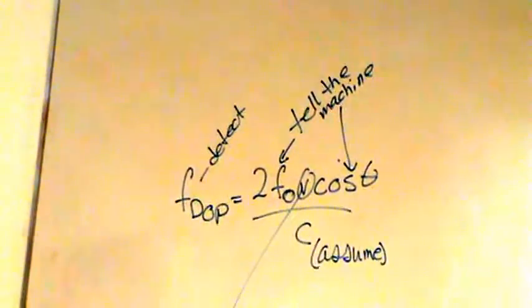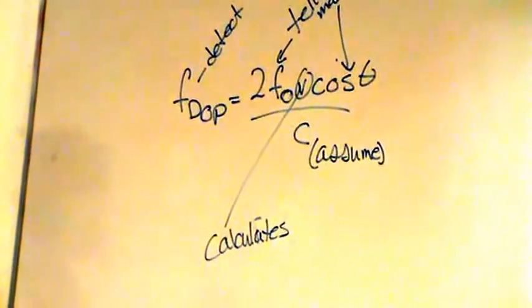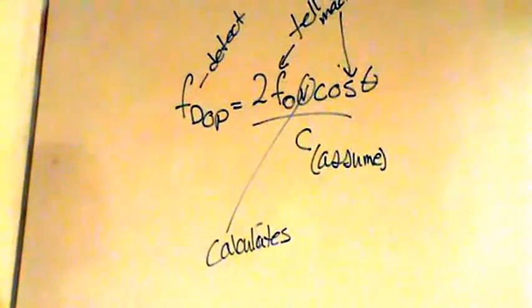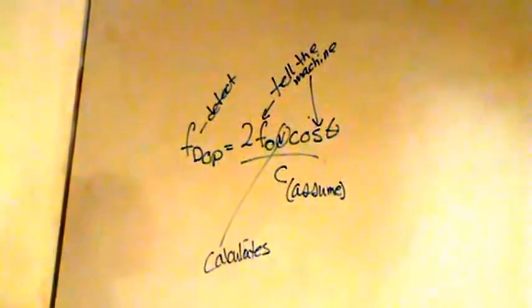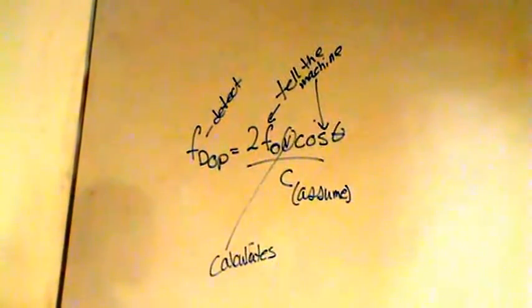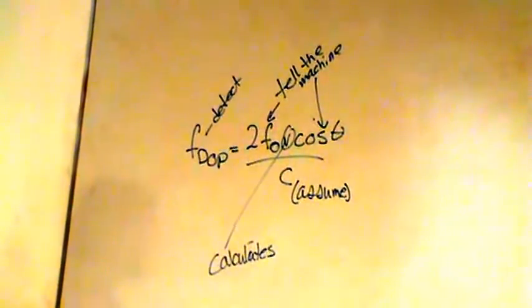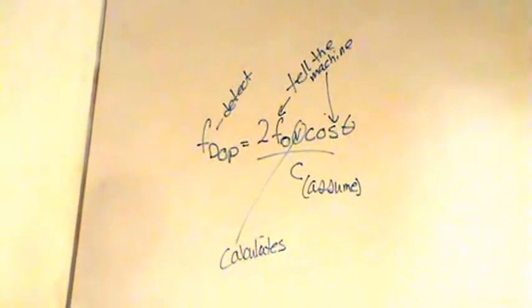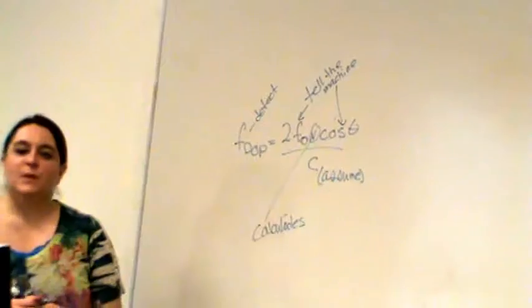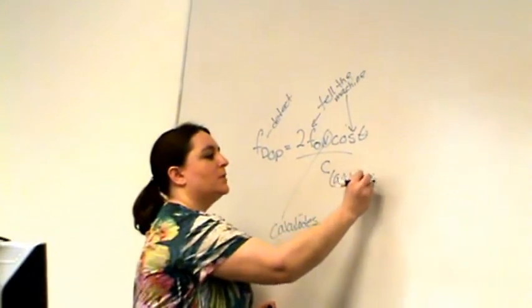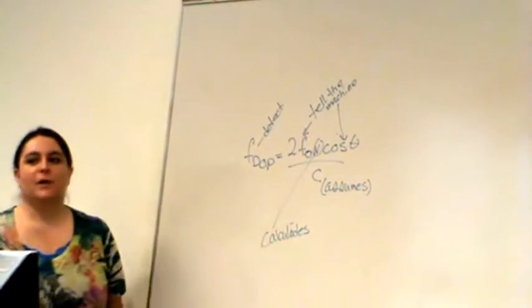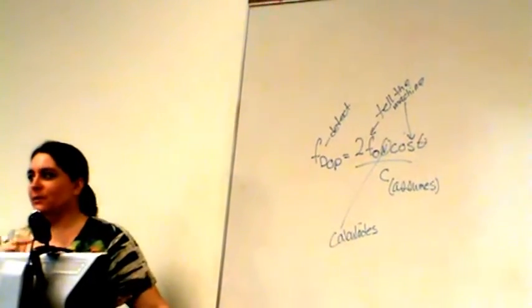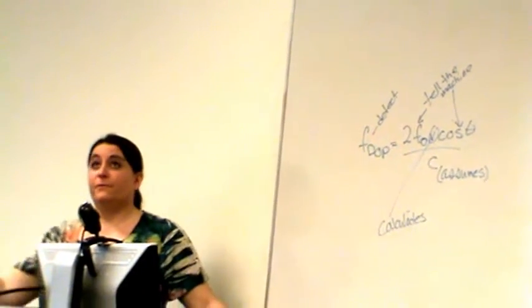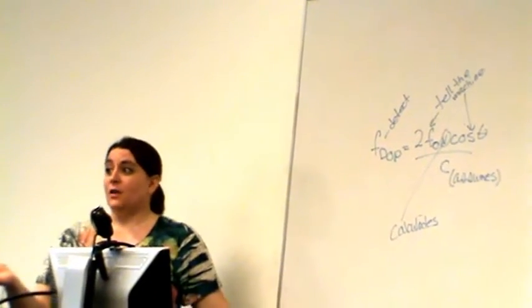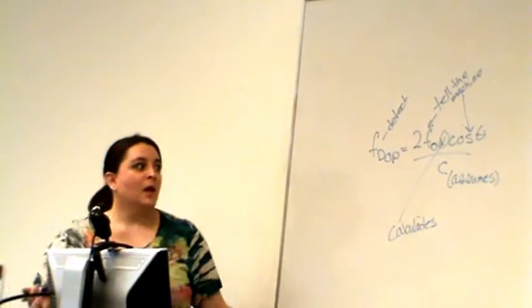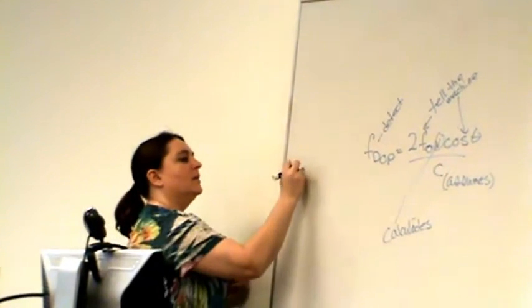So when you sit down with the machine and you turn on PW Doppler, that tells the system what operating frequency you're using, and then you turn the angle correct knob and you tell it what angle you're doing Doppler at. It assumes propagation speed in soft tissue. It assumes 1540, which again, by the way, you absolutely have to know that number backwards and forwards. And in any variation of units, I've taught you 1540 meters per second. This is worth mentioning now.